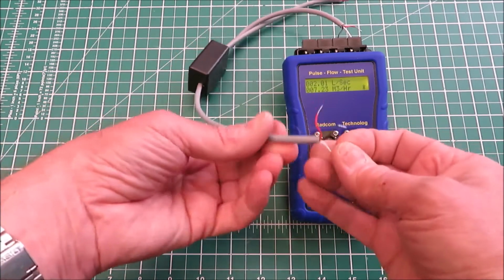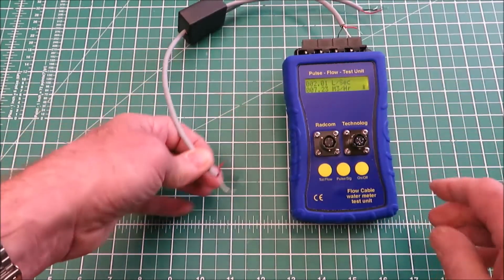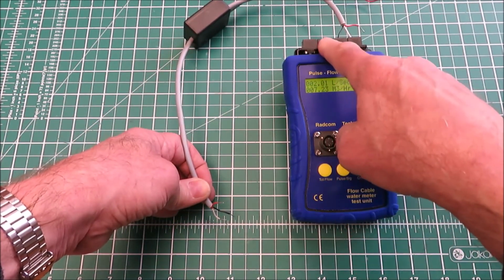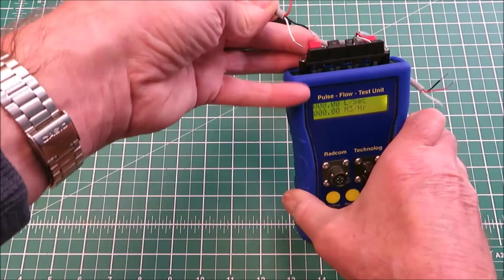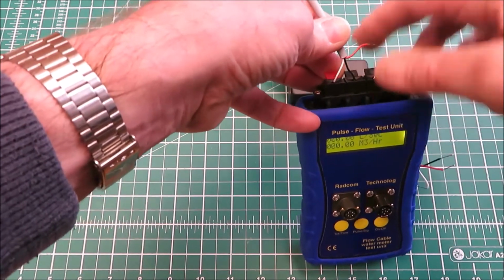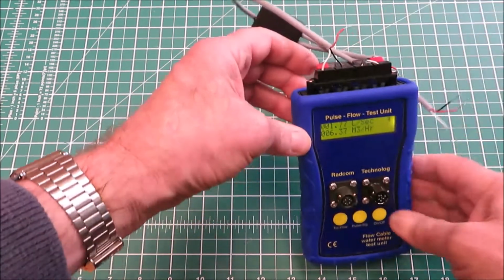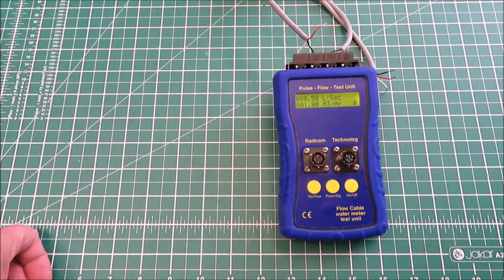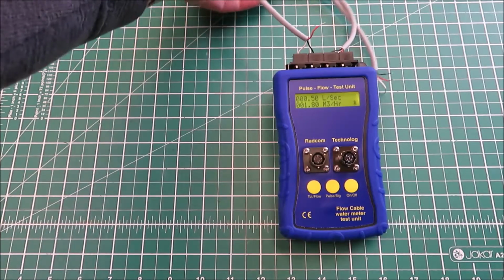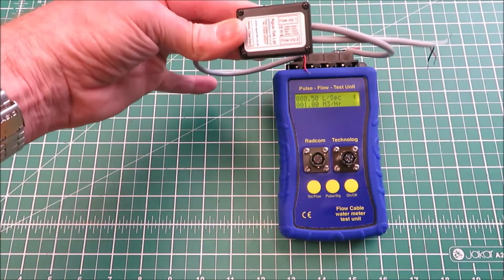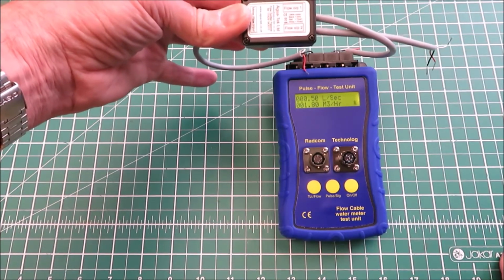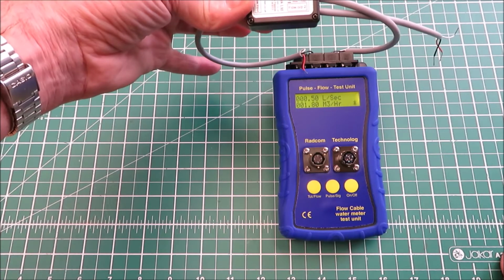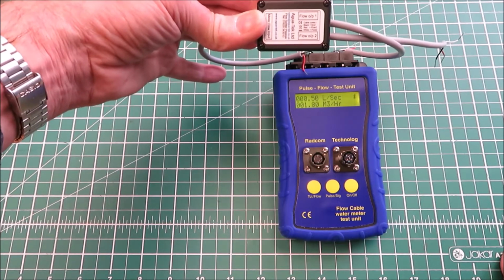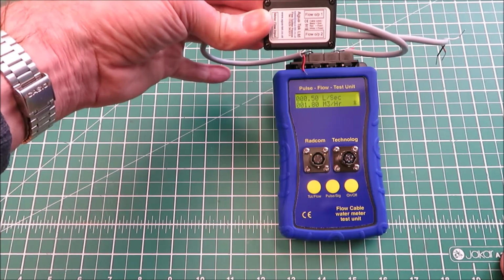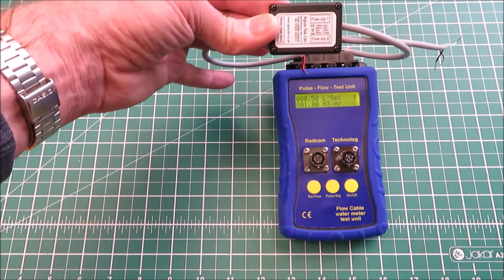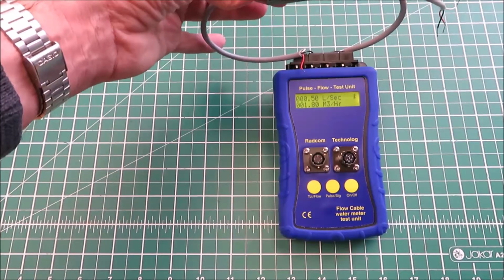Now what we can do is connect this, because the pulse test unit actually puts a pulse output on these 2 connectors. I could pop the black wire into there and the white wire into there, and now you can see that it's putting a pulse out which is going into the splitter, through the splitter and out on the black and white wire. And that is one way of testing the passive splitter using a pulse test unit, or 2 ways even, one by touching the wires together, and the second method by actually using the pulsed output from the pulse test unit.